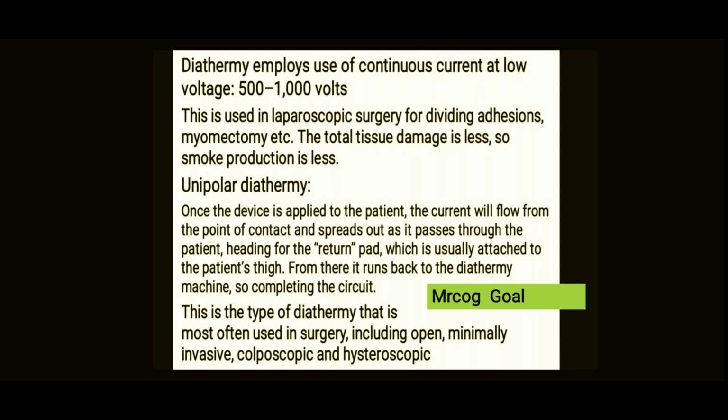The diathermy employs continuous current at low voltages, that is 500 to 1,000. This is used in laparoscopic surgeries for division of adhesions and myomectomies, right? The total tissue damage is less, so the smoke production is less.